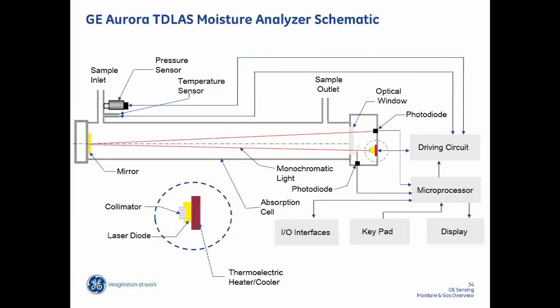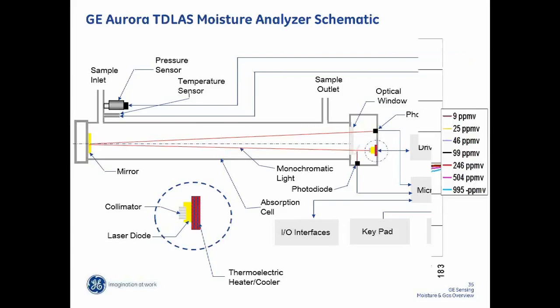At the same time, we measure the pressure and the temperature of this system. So the nice thing about that system, let me just go back for a second, is that it's completely inert, in the sense that there isn't a sensing surface in the wetted flow of the gas. There's really nothing to wear or degrade over time. It's a fully non-contact system, and it's a very fast-acting system.